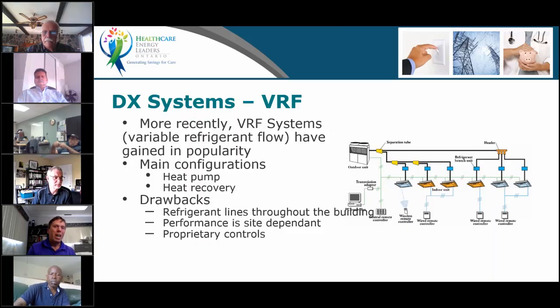The last system before I pass it on, and the only reason I put it in there is because we see it more and more. You should not see that very much in most spaces in the hospital because they're not allowed. But those are VRF systems, variable refrigerant flow. So you will have many what we call heads. You'll see that in type 3 spaces sometimes. So those are all heating or cooling units. They're connected to a given outdoor unit, but they can actually be either a heat pump. So all of those units will be either heating or cooling when it's a heat pump model. If it's a heat recovery model, each of those units can be in a different mode.